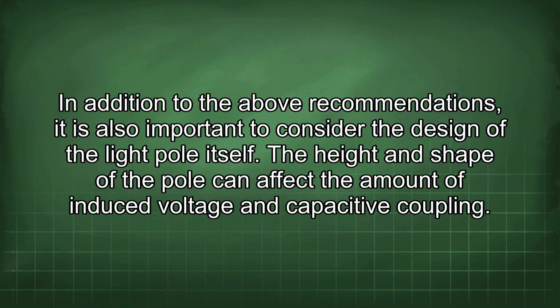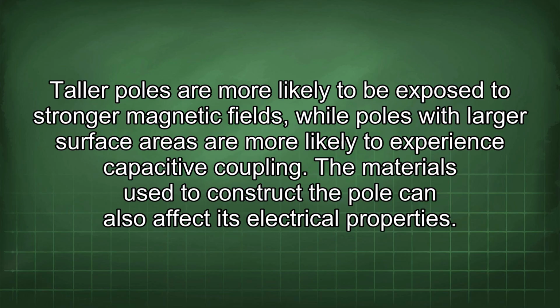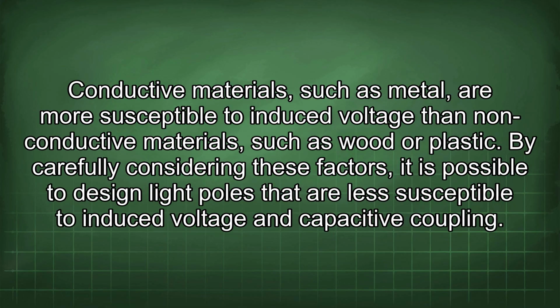In addition to the above recommendations, it is also important to consider the design of the light pole itself. The height and shape of the pole can affect the amount of induced voltage and capacitive coupling. Taller poles are more likely to be exposed to stronger magnetic fields, while poles with larger surface areas are more likely to experience capacitive coupling. The materials used to construct the pole can also affect its electrical properties. Conductive materials, such as metal, are more susceptible to induced voltage than non-conductive materials, such as wood or plastic.